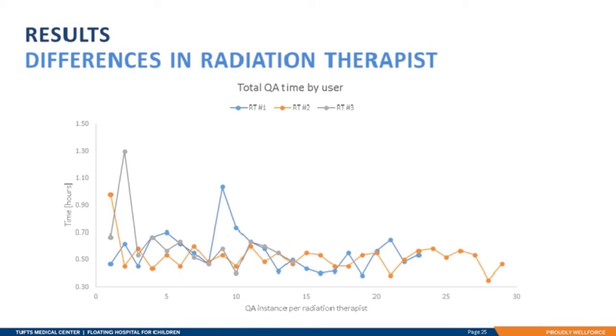The instance where the QA time exceeded an hour correlated with times that the Machine Performance Check had to be performed multiple times in order for the results to properly record. For us, this ruled out a training issue or an initial break-in period, and more pointed to just normal daily variation. Since there were enough instances of breaks during the QA time, however, we did sum the time from the individual tests as opposed to simply taking the time the QA was started and finished. This focused on the time that the QA was actually being performed and removed these breaks.